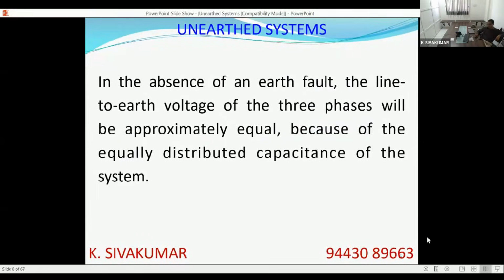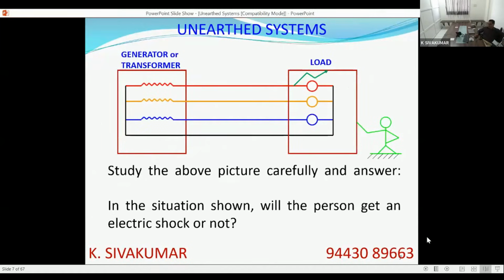Suppose there is no earth fault in the system. The three-phase line to earth voltages will be approximately equal, because we presume, to simplify things, that the capacitance is equally distributed. Now, do not think about very complicated capacitive coupling. Just look at this picture. If this system is unearthed and the R phase is touching the metal enclosure of the load, and a person is in direct contact with the metal enclosure, assume the worst conditions: wet foot, barefoot, wet floor.